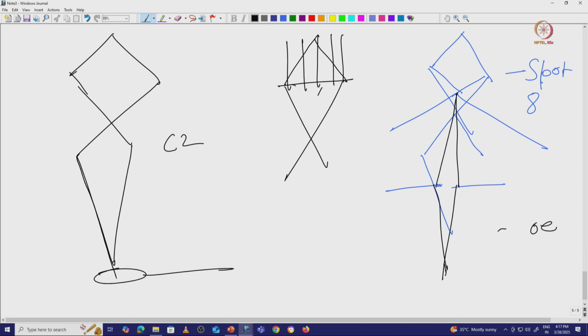If we make the beam focused on one particular point, is this a good idea, controlling your C1 lens current and C2 lens current in such a way that your electron dose goes and falls on your sample focused on one particular position? If so much electron dose is concentrated in one particular point, it is going to damage all the amorphous ice and melt it. So this is definitely not a good idea.